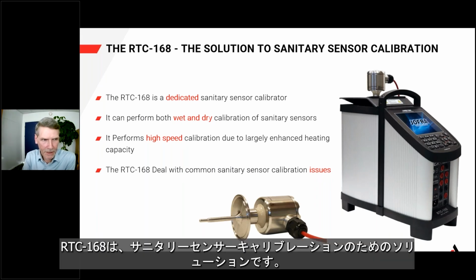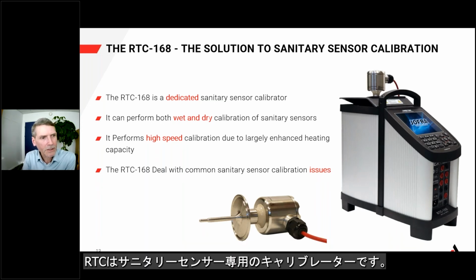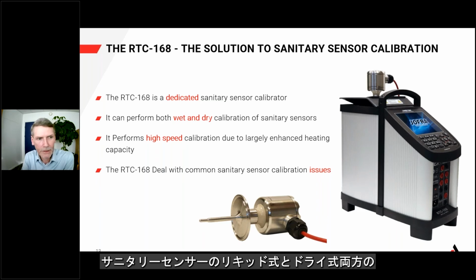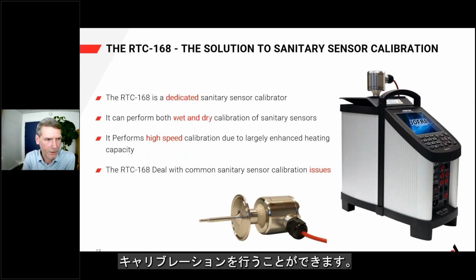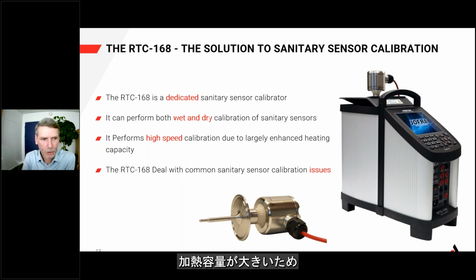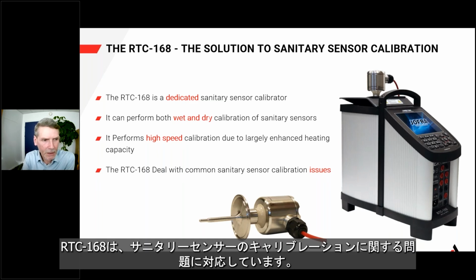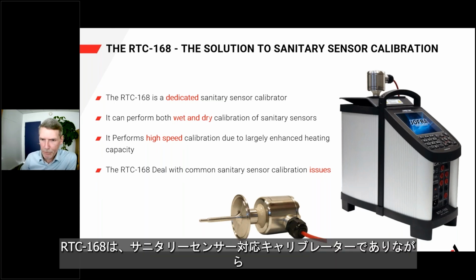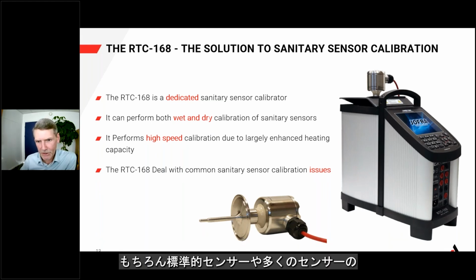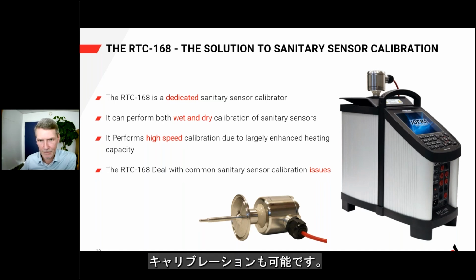The RTC168 is the solution to sanitary sensor calibration. The RTC is a dedicated sanitary sensor calibrator. It can perform both wet and dry calibration of sanitary sensors. It performs high-speed calibration due to the larger enhanced heating capacity. The RTC168 deals with common sanitary sensor calibration issues. And on top of being a dedicated sanitary sensor calibrator, the RTC168 can naturally still perform calibration of standard sensors and take many sensors in a run.